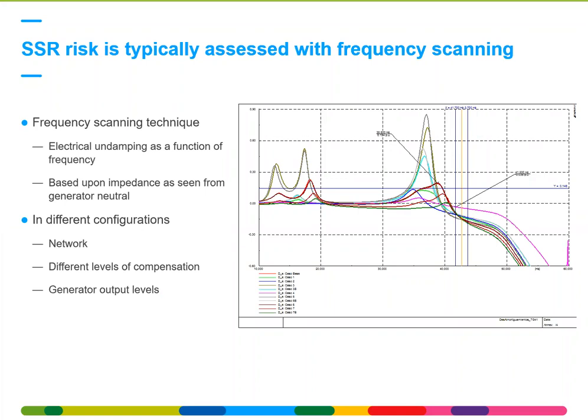So the simulation is actually uncoupled. You only regard the electrical one, and you check in the grid which frequencies are prone to have interaction, and if your mechanical torsional natural frequencies are coinciding with these electrical ones, there's a potential for interaction and issues of resonance. These are checked in many different configurations of the grid. So typically every time there's a change in the grid configuration, this type of risk assessment should be renewed.